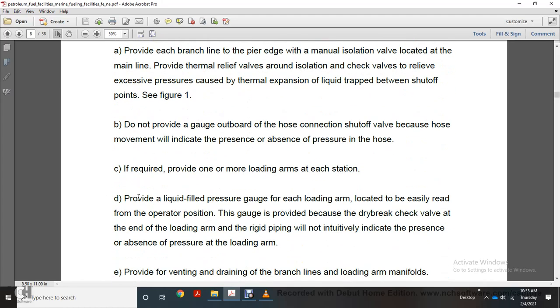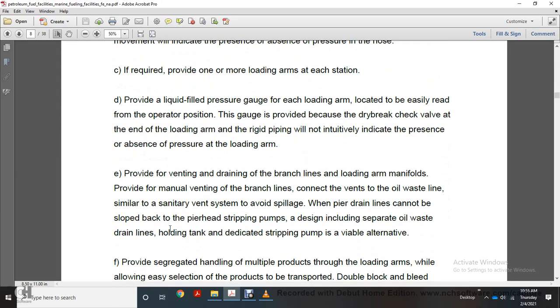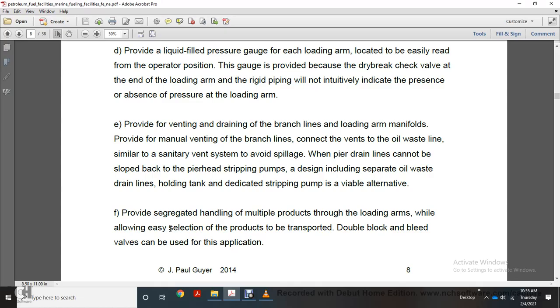Do not provide a gauge outboard of the hose connection shutoff valve, because hose movement will indicate the presence or absence of pressure in the hose. If required, provide one or more loading arms at each station. Provide a liquid-filled gas pressure gauge for a loading arm, located to be easily read from the operator's position. The gauge is provided with a dry break check valve at the end of the loading arm, so the rigid piping will not initially indicate the presence or absence of pressure in the loading arm.